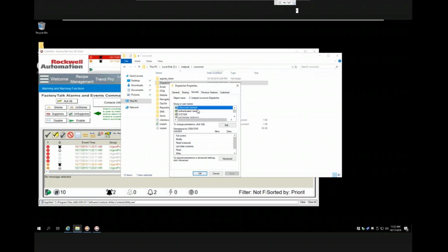If you are in a workgroup environment, so you don't have a domain, what that means is that you'll need to create a Windows user account that is on the WIN-911 system and on the remote system that has the same name, same password. If you're in a domain, it's a little bit different. You just add that particular domain user here, or you could create a new domain group, maybe call it WIN-911 access, and then put that into this security section here, and that's how you can control who can access this WIN-911 system. So that is what I mean by Windows authentication.